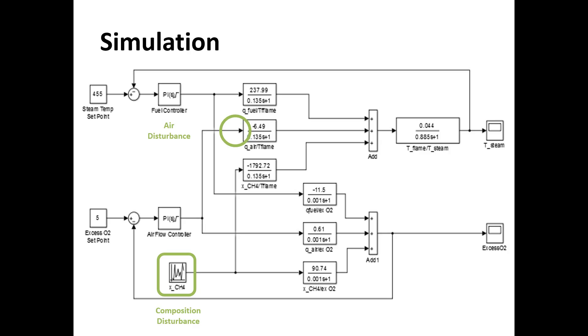You'll also notice that the amount of air acts as a disturbance within the steam temperature loop because extra air is just wasted energy that we're sending out in nitrogen. Also the amount of fuel acts as a disturbance within the air loop because more fuel requires more oxygen.